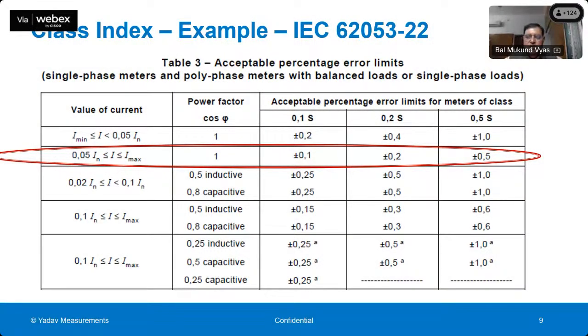So this is an example from an IEC standard, but of course these tables are very similar in the Indian standard or even the OIML standard. They are very similar. So you can see there are influences. Unity power factor. So when you say that the meter is 0.5, it is plus minus 0.5 within this current range only, 0.05 In to Imax, right? For other current values and other power factor values, the specified accuracy limits are higher. So when we have said the meter is class 0.5, it is within plus minus 0.5 only in this current range at unity power factor, under reference condition, under balanced conditions, and so on. So very important to understand this.